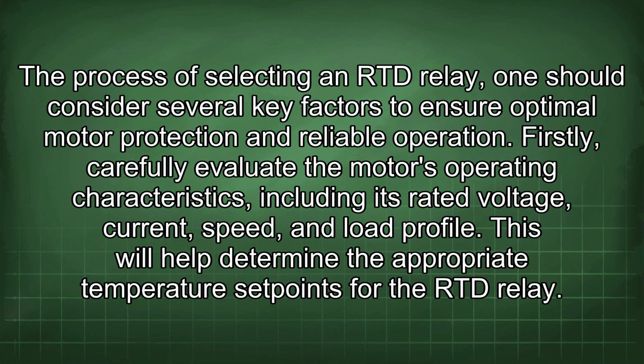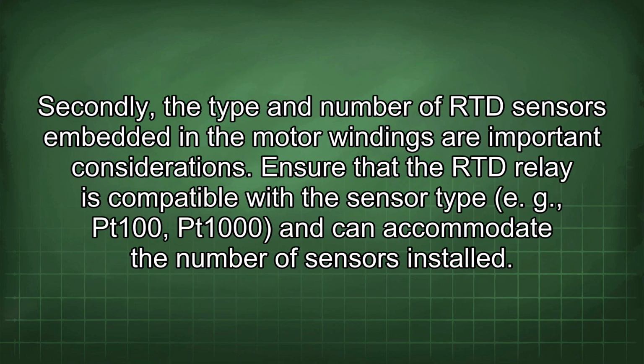In the process of selecting an RTD relay, one should consider several key factors to ensure optimal motor protection and reliable operation. Firstly, carefully evaluate the motor's operating characteristics, including its rated voltage, current, speed, and load profile. This will help determine the appropriate temperature set points for the RTD relay. Secondly, the type and number of RTD sensors embedded in the motor windings are important considerations.